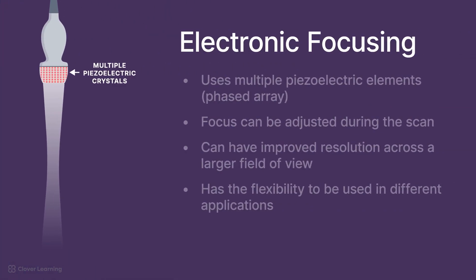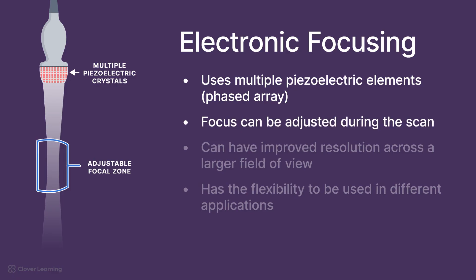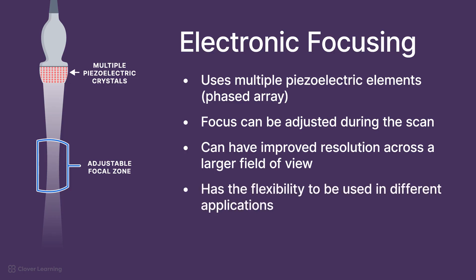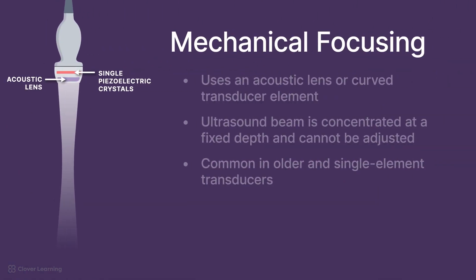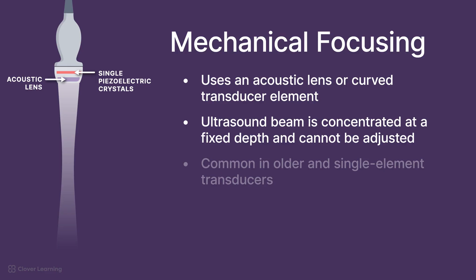Electronic focusing is achieved using multiple piezoelectric elements in the transducer in a controlled sequence, often called phased array technology. Electronic focusing can be adjusted during the scan, can have improved resolution across a larger field of view, and has the flexibility to be used in different applications. Mechanical focusing is achieved by using an acoustic lens or curved transducer element to concentrate the ultrasound beam at a fixed depth. So it cannot be adjusted, is less flexible, but is common in older and single element transducers.